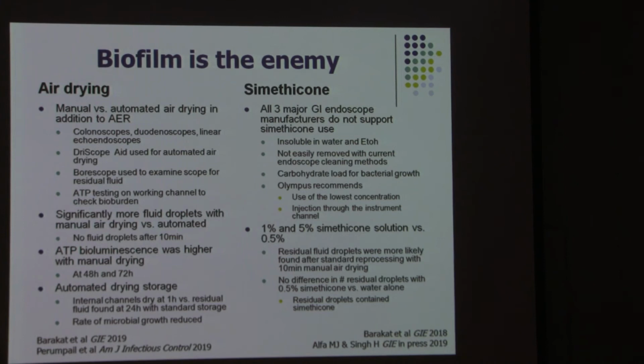Is there anything that could be done to prevent biofilm formation or decrease the risk of it? One way of doing this is additional air drying within the channel. And this study actually looked at manual versus automated air drying, with a kind of machine that does the automated air drying after the scopes underwent high-level disinfection.